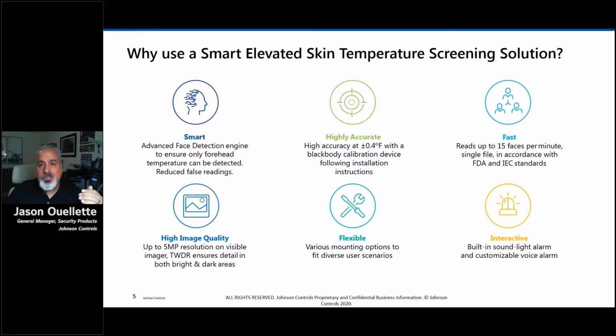And so we're able to get students and faculty alike, with a proper setup environment, and we're able to do that in less than half a second, recognizing that face and then converting that to a temperature. But really, one of the most important points that I would stress is the accuracy. This solution has been tested independently by Underwriters Laboratories to the global standard for human febrile body surface temperature detection, known as IEC 80601-2-59. The FDA, in their view of these devices, says your accuracy has to be at least 0.5 degrees Celsius, that's 0.9 degrees Fahrenheit. Our solution has been verified to achieve 0.2 degrees Celsius accuracy, or 0.4 degrees Fahrenheit.